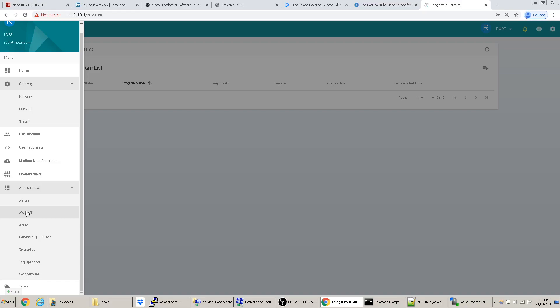One use case is logging data using Things Pro and reading it all, then setting when to send it to your SCADA system. Instead of SCADA continuously polling all the time and using lots of memory or bandwidth, you could log information here and even write a program that decides what data is relevant and sends only that back to SCADA, saving bandwidth.